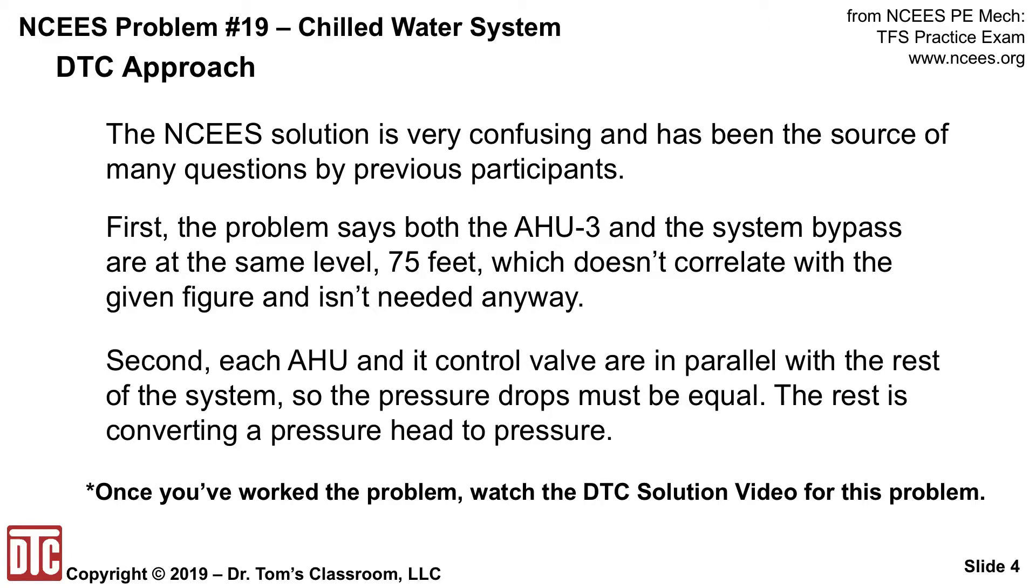And then, as you see in the diagram, each air handling unit and its control valve is parallel with the rest of the system, so the pressure drops across each one of those must be equal. The rest is just converting a pressure head to a pressure.